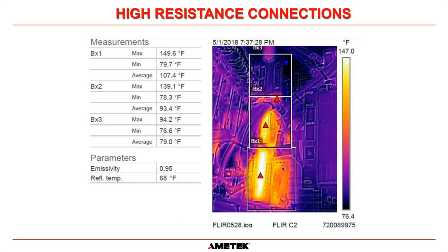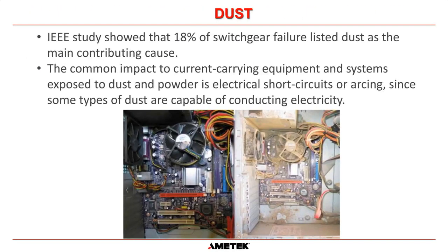And it would never have been caught because the choke is only acting as a filter, and you would have to have full load on the system basically to be able to see that the choke wasn't filtering as it should, and the total harmonic distortion of the output of the UPS would have gone up significantly. But when this was being tested and there was light load on the system, the output would have looked pretty normal. So this is a great example of thermal imaging where we found that this choke wasn't actually connected in circuit. So we had to go in and do a remedial action for that. So connection issues are true. They are out there all the time, and you need to pay attention to them.